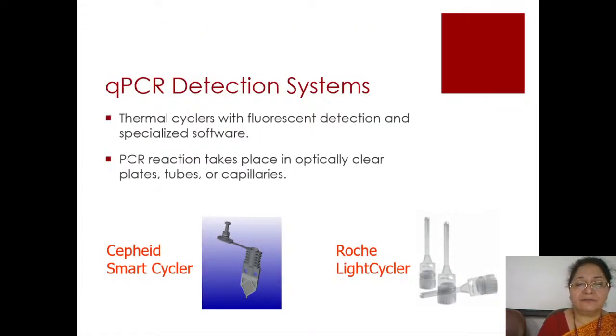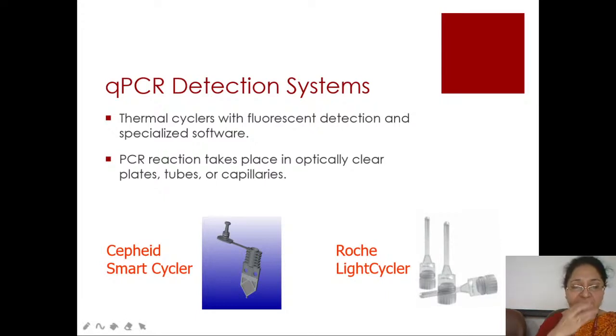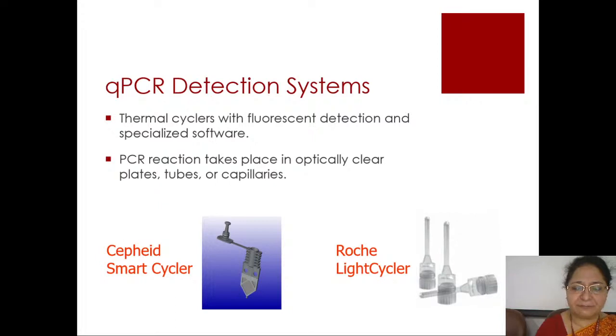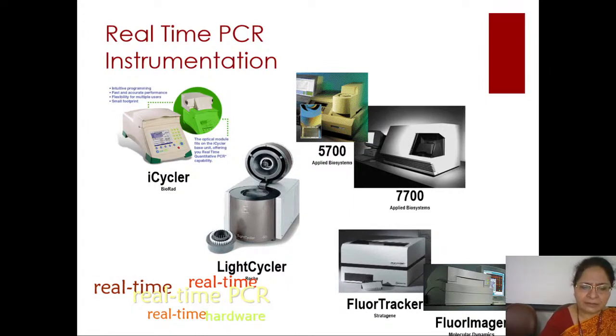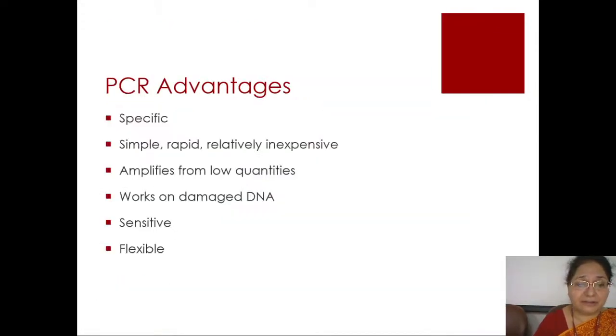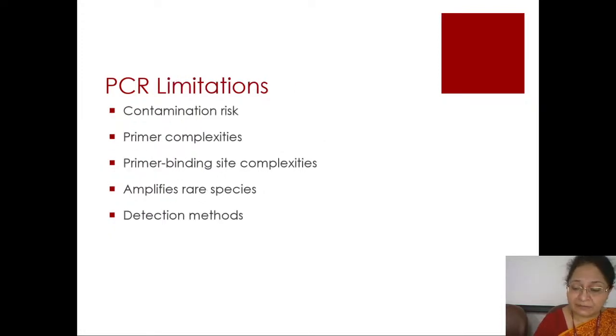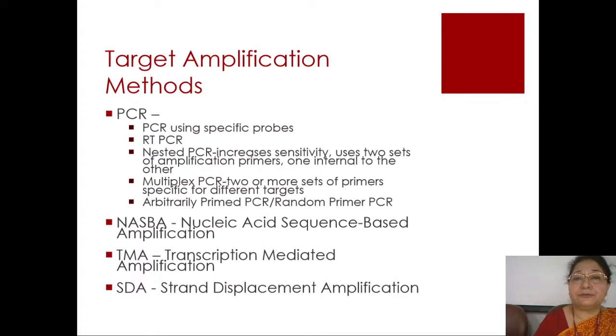In the TaqMan assay, as strand extension occurs, the fluorescent molecule and quencher are cleaved from each other, allowing fluorescence to appear. In the molecular beacon, the hairpin-loop structure holds the fluorophore and quencher together until the beacon binds its target, separating them and generating fluorescence. We have several commercial machines using these principles — such as the Smart Cycler and Roche LightCycler — along with many others including ABI systems, iCycler, and BioRad instruments. In the current SARS-CoV-2 epidemic, these instruments have been very widely used, enabling laboratories that had not previously done molecular diagnosis to begin doing so.